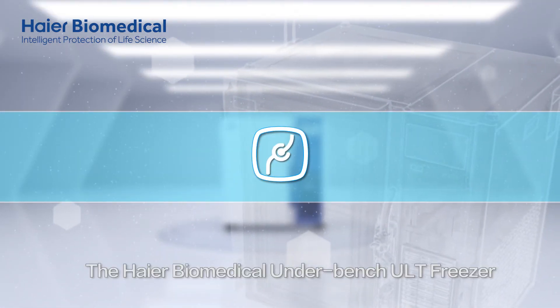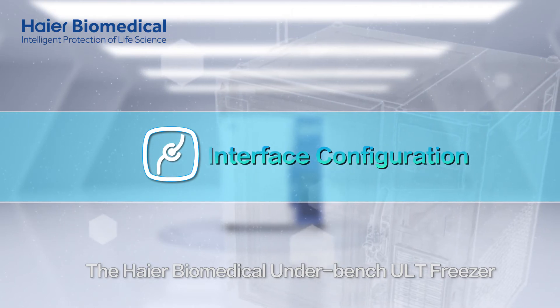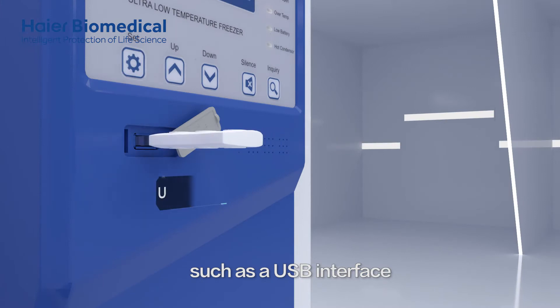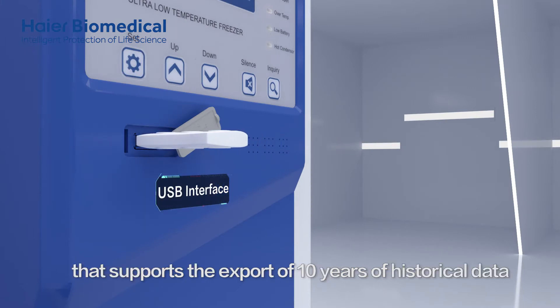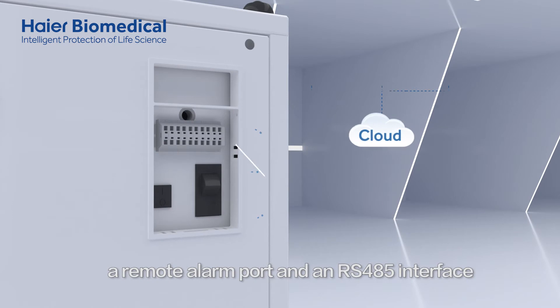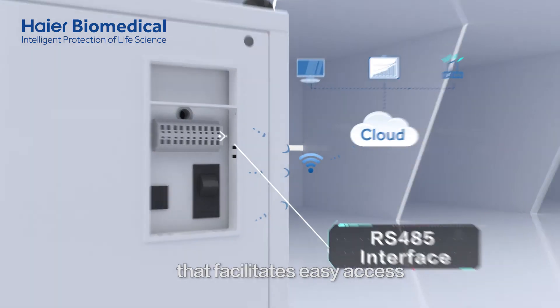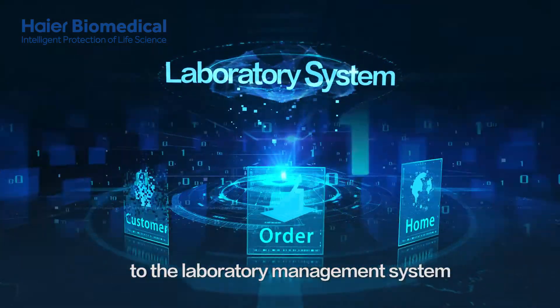In addition, the Haier Biomedical Underbench ULT Freezer is designed with various interfaces such as a USB interface that supports the export of 10 years of historical data, a remote alarm port, and an RS-485 interface that facilitates easy access to the laboratory management system.